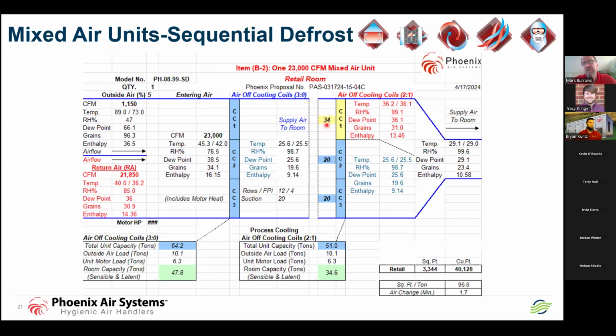A little bit of frost is okay, but if we bridge the fins with ice, you're never going to defrost the coil. This fan is running continually at 23,000 CFM. When it's time to defrost via a timer, we still want liquid in all 3 coils all the time. All we do on the top coil, we're still feeding it with cold liquid. We change the dual pressure suction regulator to 34 degrees or 50 pounds in the case of ammonia. I can still catch the air at 45 degrees on the entering side of the coil. I can warm this coil up from the inside out, so to speak. We can defrost these coils in about 10 minutes.